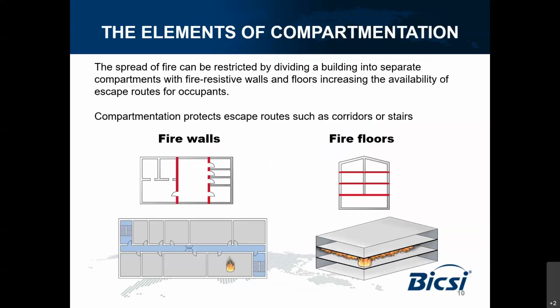The concept of compartmentation is basically restricting the fire and smoke to a certain area of a building. As I outlined, it also buys time for people to escape from the building. It also protects the equipment and the facility inside the building. Now from the picture on the left-hand side, you can see the fire-rated corridor, the blue part. All the fire-rated walls surrounding the corridor protect people so they can escape through the protected exits.